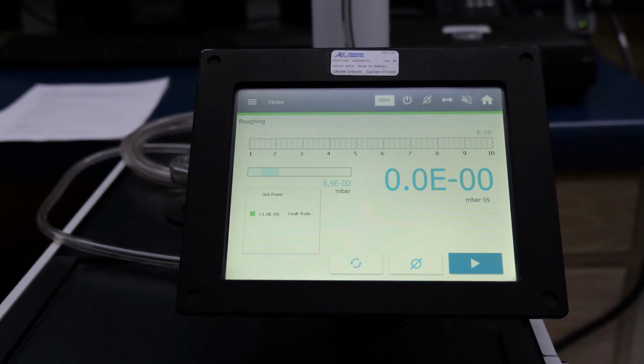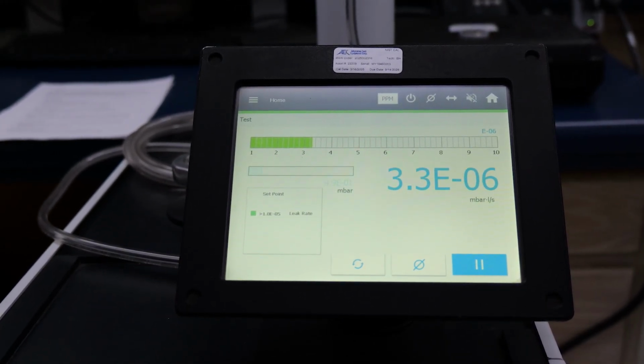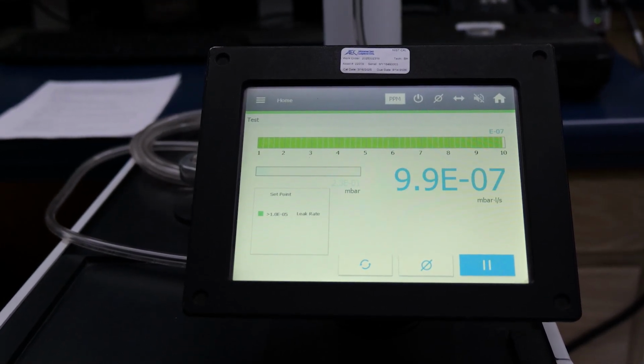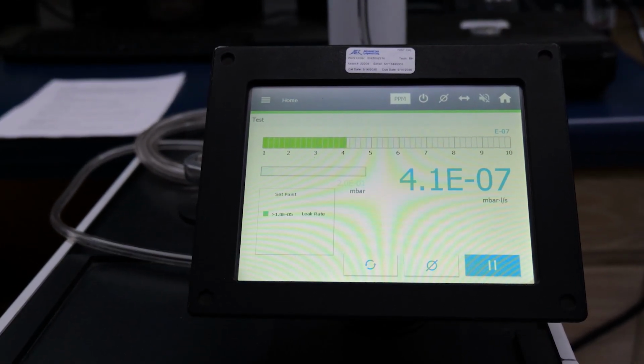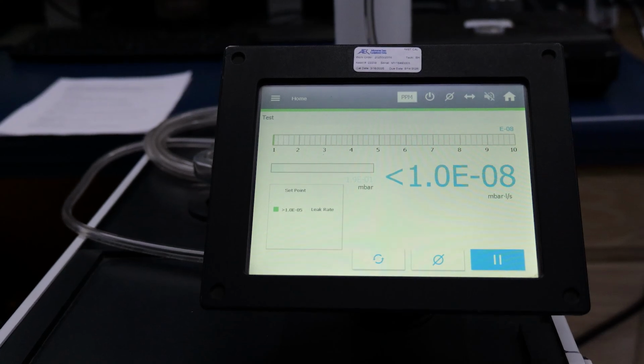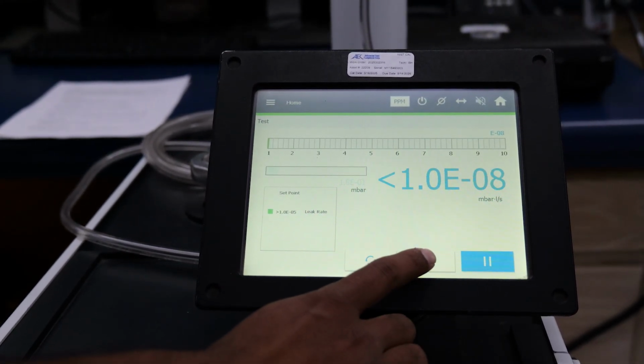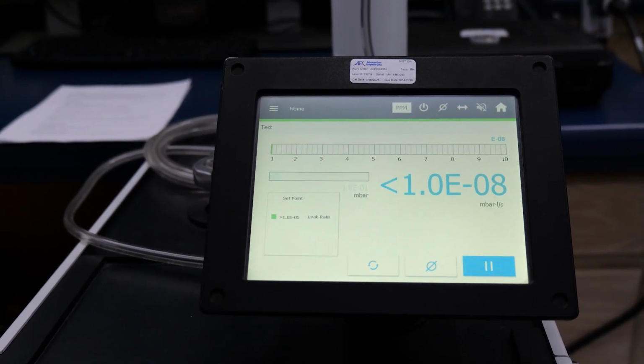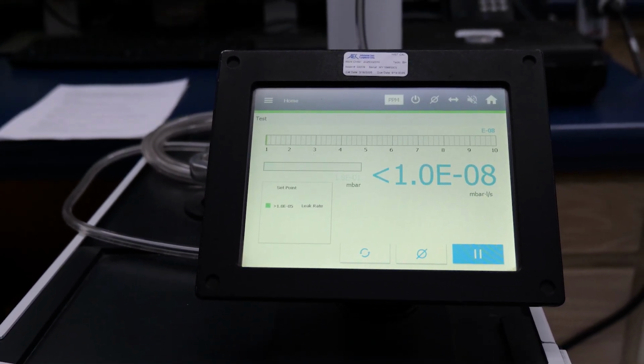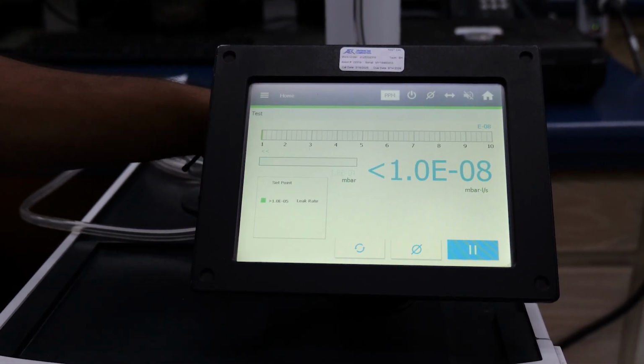It'll go through the roughing sequence. And you should expect to see a leak rate of less than 1 to the -8 millibar. And you can always zero your test out to make sure it's zeroed. And then we can go by here checking for leaks.